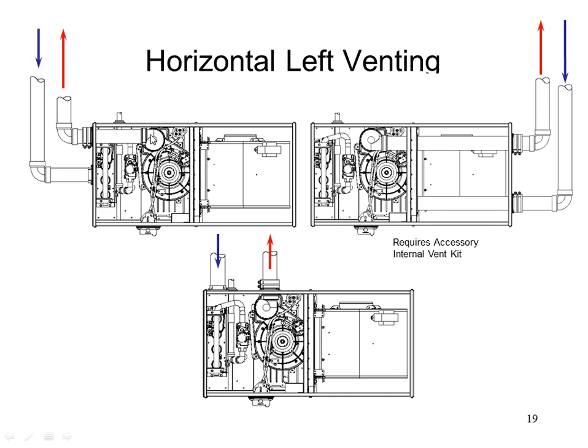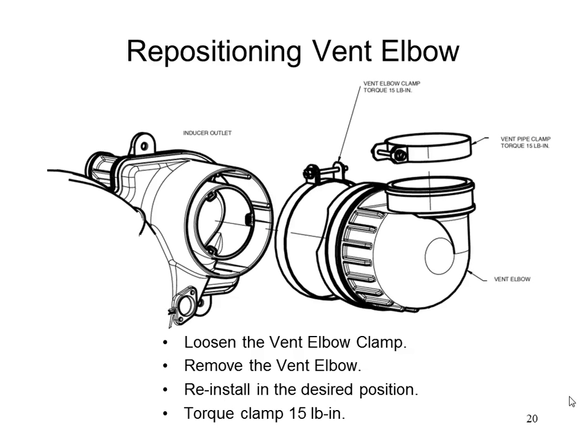Over here on the left top drawing, that's how that guy would ship from the factory with the elbow pointing that way. I could also rotate him so he comes and goes out what is now the top of the furnace cabinet, or I can rotate him 180 degrees and cut through the blower housing again. Same issues. I've got to have the venting kit, and I'm blocking off my access if I do that scenario. But if you have to do it, you can. And there's also a similar drawing like this for right-hand venting.